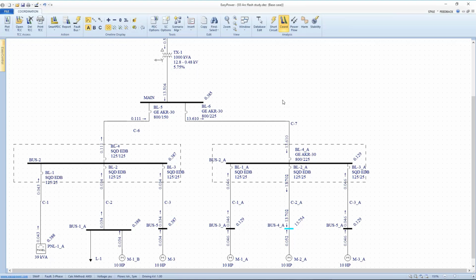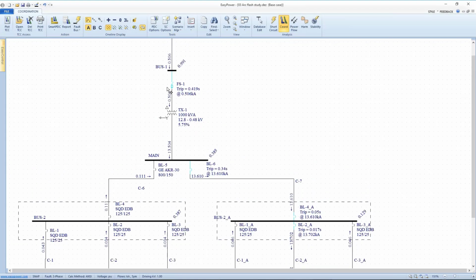To that end, once I've calculated these short circuit currents for a single bus fault, the tool allows me, by invoking this little keyed item at the top, sequence of events, it shows me now if I have a fault at this bus, that this breaker will trip in 17 milliseconds, this breaker will trip in 50 milliseconds, this breaker will trip in 340 milliseconds, and finally my fuse trips in 419 milliseconds, or just under half a second.